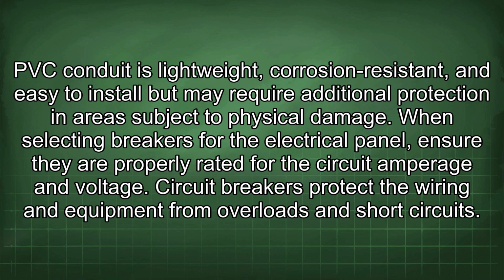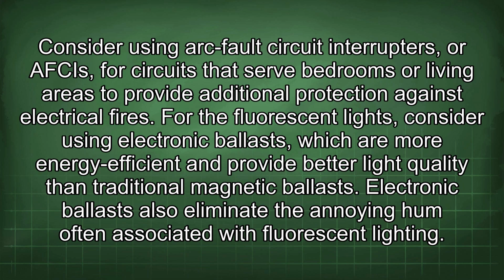When selecting breakers for the electrical panel, ensure they are properly rated for the circuit amperage and voltage. Circuit breakers protect the wiring and equipment from overloads and short circuits. Consider using arc fault circuit interrupters, or AFCIs, for circuits that serve bedrooms or living areas to provide additional protection against electrical fires.